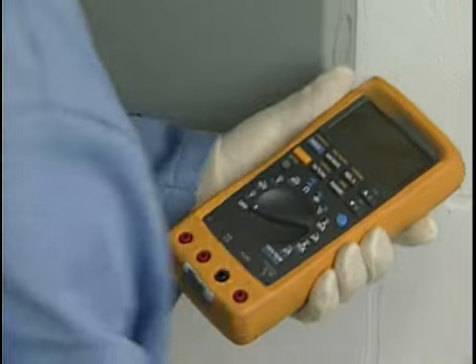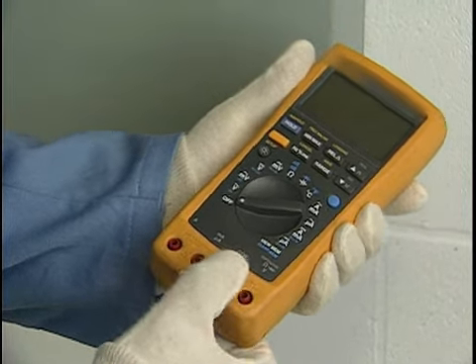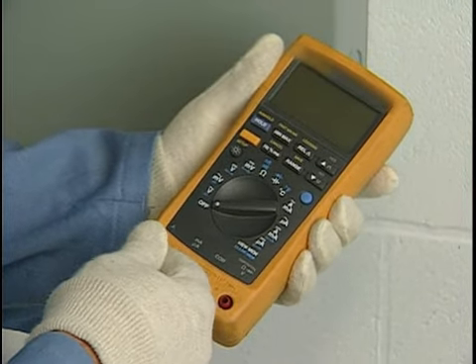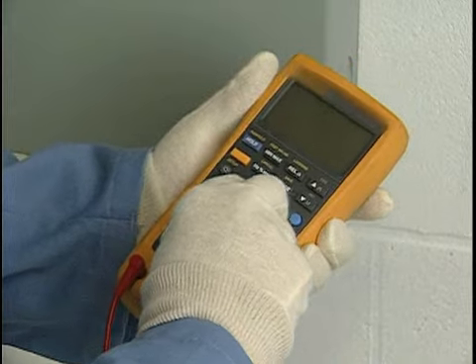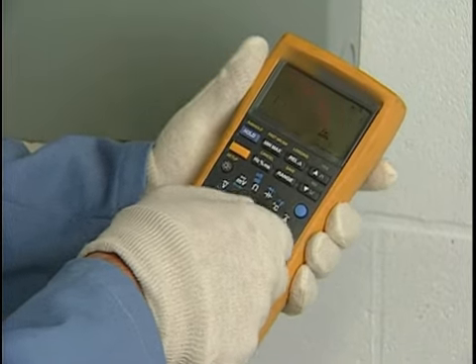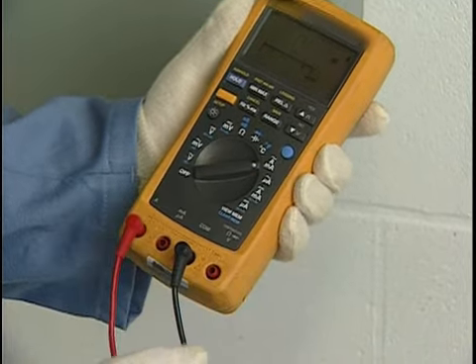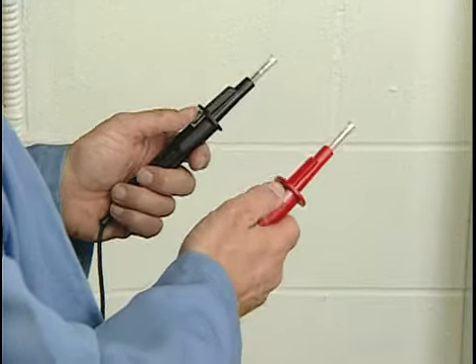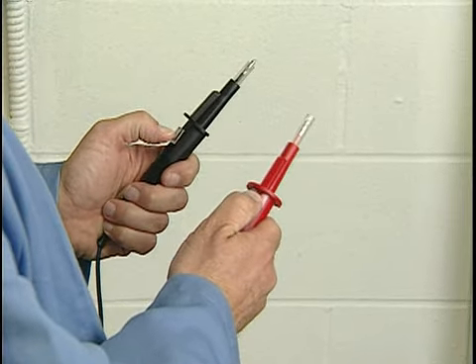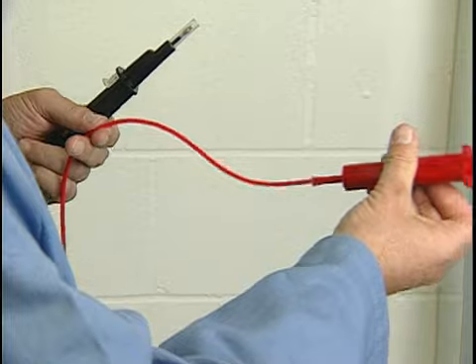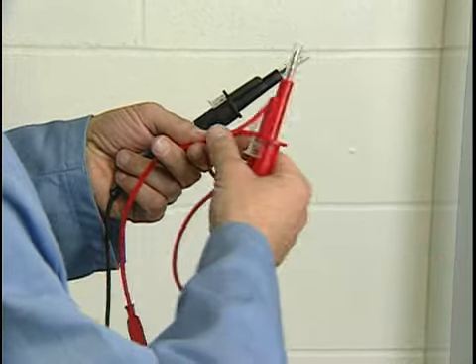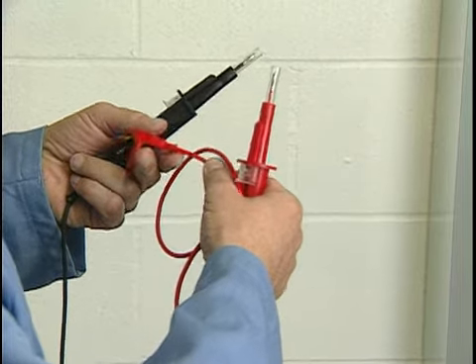Replace your multimeter with one that has the highest category and voltage rating you'll require, and do not use it without fused test leads. Only use properly approved and properly rated multimeters and fused leads. Always check your meter and fused leads to ensure they're in good operating condition. See the accompanying health and safety guideline reference on this disc for information on how to check your meter.